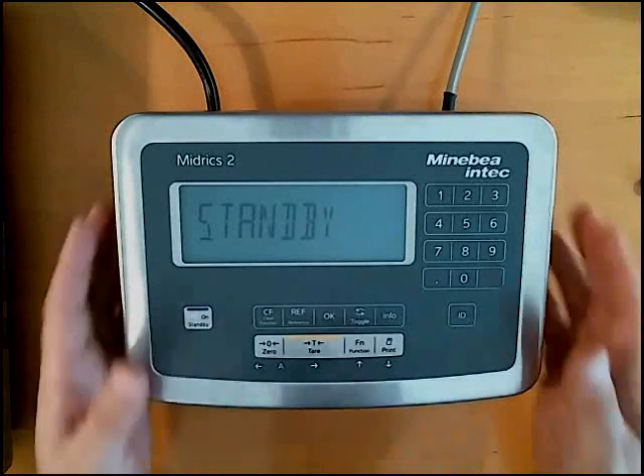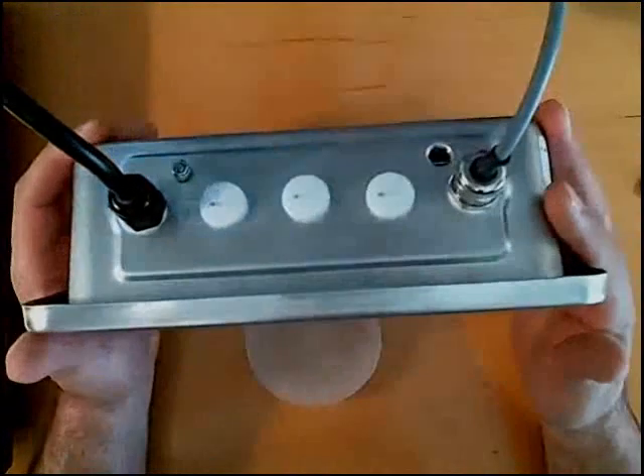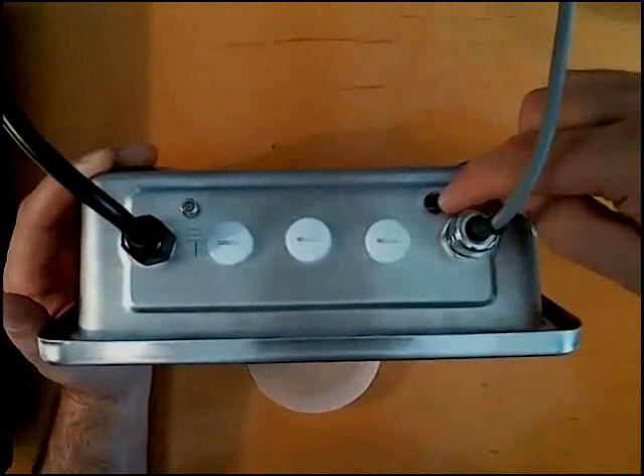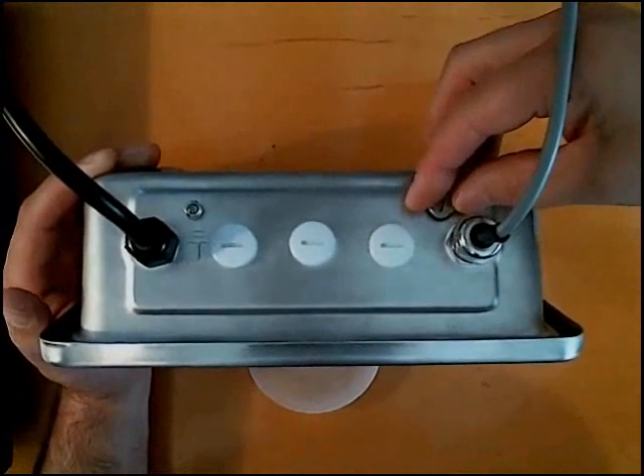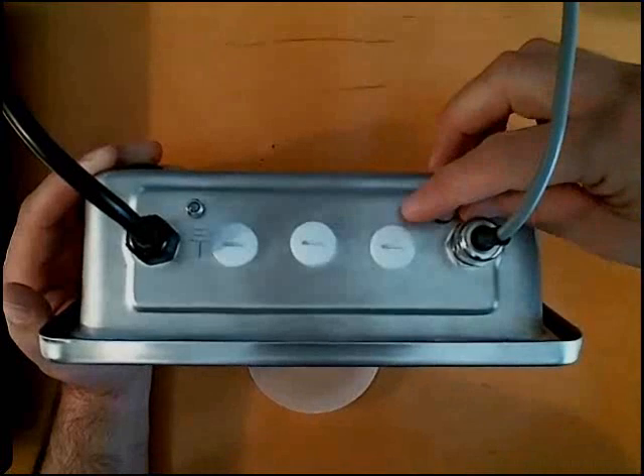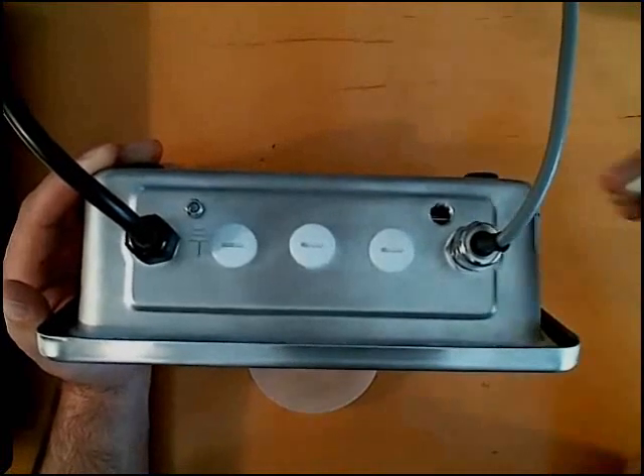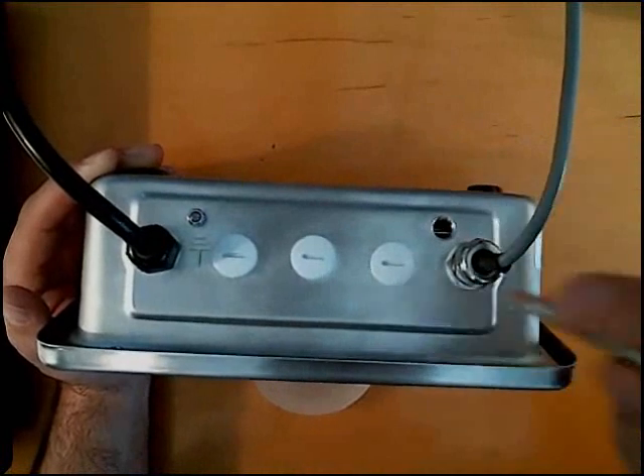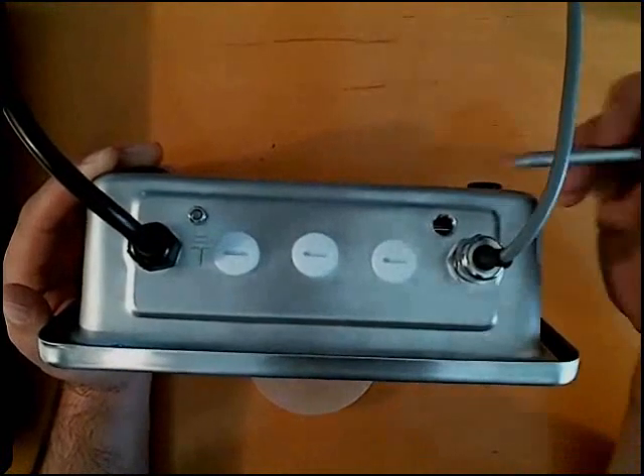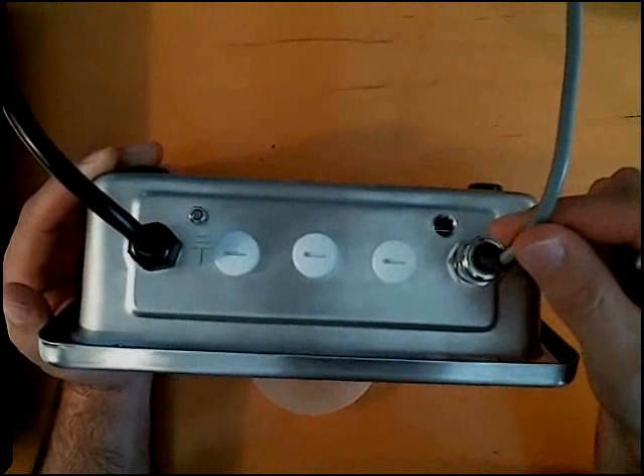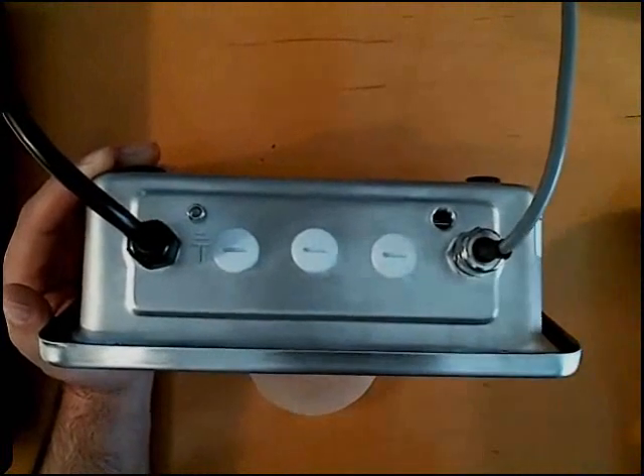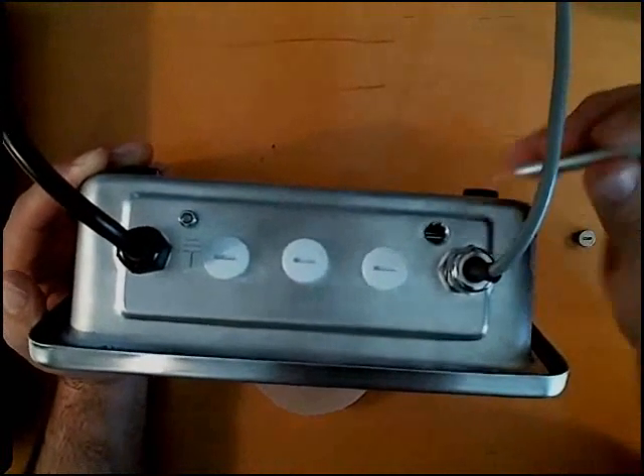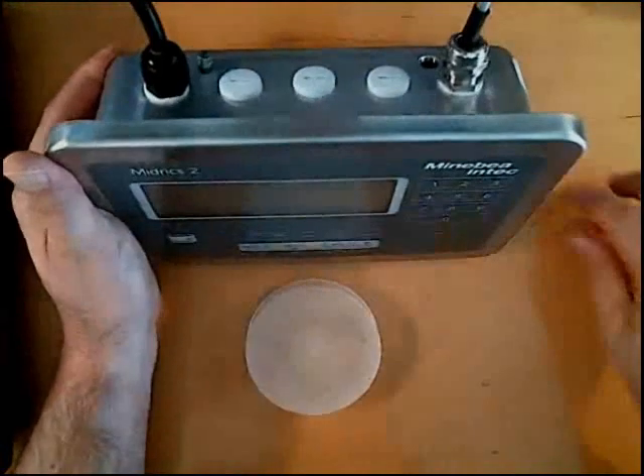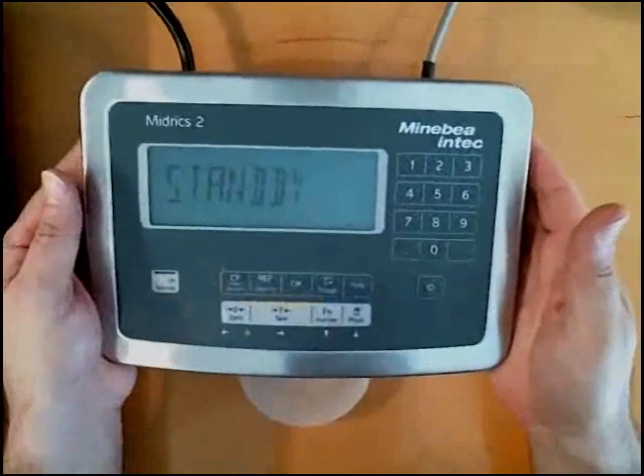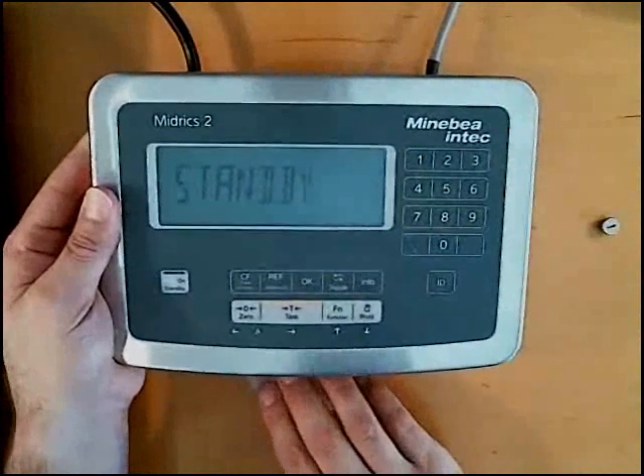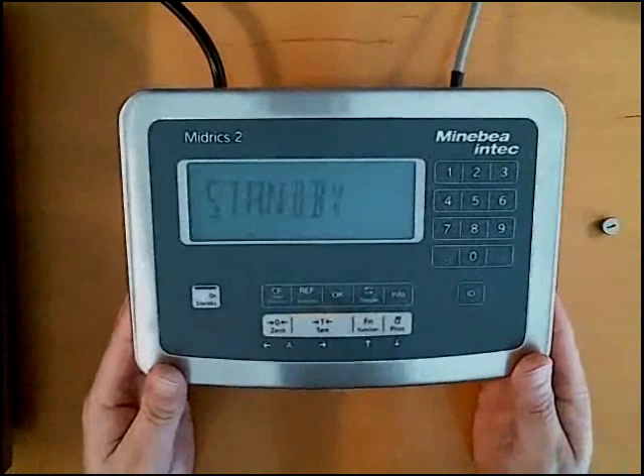The first thing you need to do is go to the back side of the unit, and you'll notice right here there's a hole, and it will be covered by this stainless steel cap right here. When you remove this cap, you'll see that inside the hole there's a small switch. You need to make sure that this switch is in the position closest to the home run cable. That will put you into the setup mode, which will allow you to set up your A to D converter. Now, if you have a brand new unit, you needn't worry about that because it will come in the position it needs to be to set up the A to D converter.